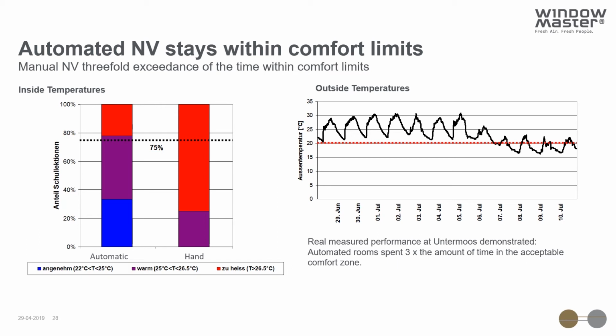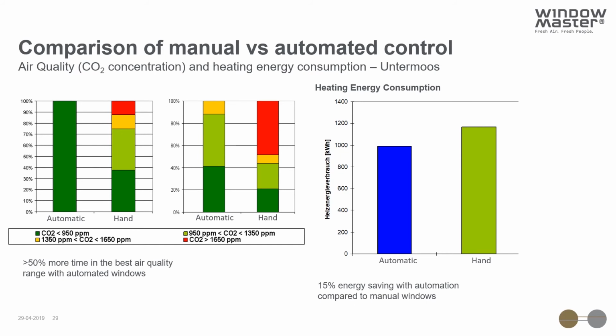What we were able to see is that those classrooms with manual windows, as shown in the right-hand bar of the graph, saw much higher temperatures for a lot more of the time compared with the automatic rooms. Similarly, in terms of air quality, those rooms with automated windows demonstrated really good levels of air quality most or all of the time compared with those with manual windows. At the same time, we were able to deliver a 15% energy saving in those spaces with automated windows compared to manual windows.